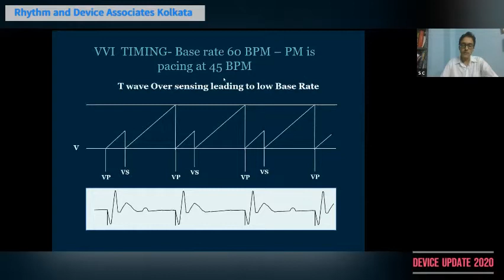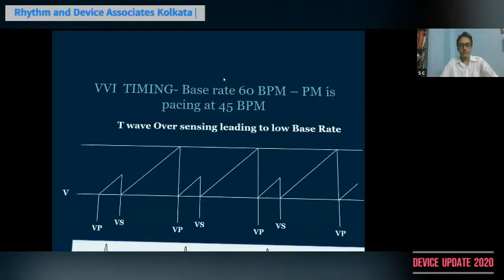So basically the VP to VP interval is prolonged and the pacemaker is actually now pacing at somewhere around 45 beats per minute, although it was supposed to pace at the lowest rate of 60 beats per minute. So in a person who is pacing dependent, it can actually lead to bradycardia and erroneously low ventricular pacing rates. So your sensing, although it is good, has to be accurate. It should not pick up events other than intrinsic QRS complex in the right ventricle.